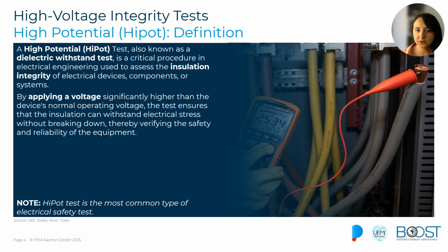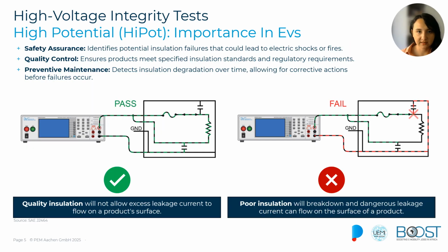The high-pot test is used in many fields, not only in electric vehicles. It is commonly used in consumer electronics, in industrial equipment, and in the EV manufacturing industry as well. During this test, by applying a very high voltage, we get a clear pass or fail condition and an indicator of whether the insulation integrity is good enough or not. If a breakdown occurs at this stage, it means that the component might be compromised, and that could lead to shock hazards, system malfunctioning, and other associated problems.